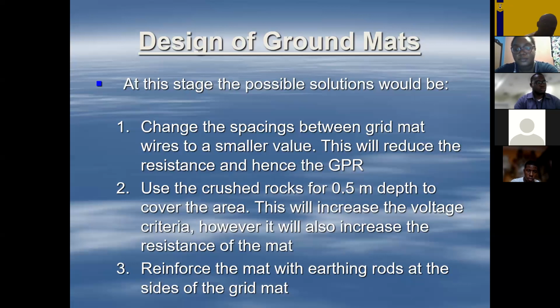The last one we have is to use rods at the side. We can drive some rods to reduce the resistance. Once you put in those rods, you need to measure the resistance. In the design, we would have calculated the resistance; when you put in the rods, you measure it.